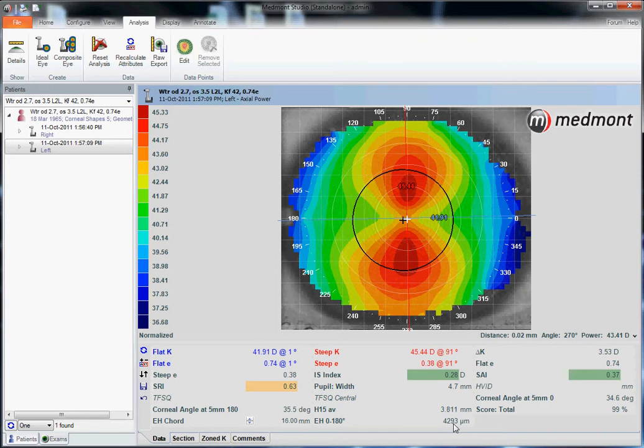There's also an estimated height chord value that you can enter specifically. For instance, if we have a scleral lens that lands at 16 millimeters and its height is calculated over a 16 millimeter chord, then the Medmont software will estimate that height to a 16 millimeter chord: 4,293 microns. Many attributes can be added to your attribute window, and this can provide you with additional details that you may require for your specific application.